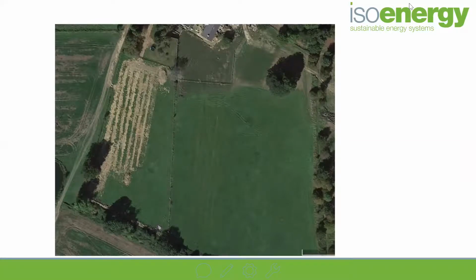The energy does move quite quickly through the earth, but it does help improve the flow temperature of the heat pump. It depends how much you're heating the pipework back up to, and that again comes down to the correct design. Because yes, you can dump heat into the collector array, but that source temperature, your glycol brine inside the collector, will stop the heat pump running if it exceeds 20 degrees. So if you're dumping too much heat into it and you heat that glycol up to about 30 degrees, then the heat pump won't work. So that might be the sort of thing that you're touching on. But again, it's all very, very bespoke when it comes to these sorts of things.